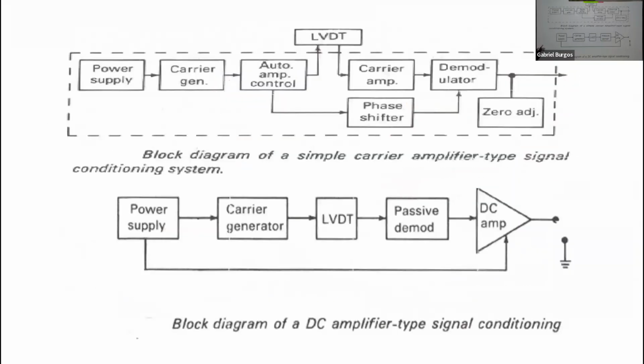Here's the electronics for an LVDT. As you'll notice, it doesn't normally use a microprocessor. You have a carrier generator to make this audio frequency, 1 to 10 kilohertz, and an automatic amplitude control. Why? Because you want to keep the primary voltage constant. Otherwise it's going to change the output.